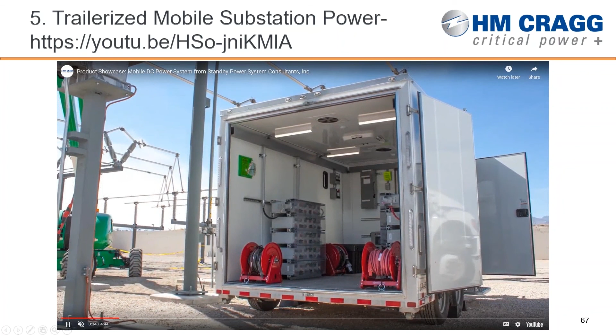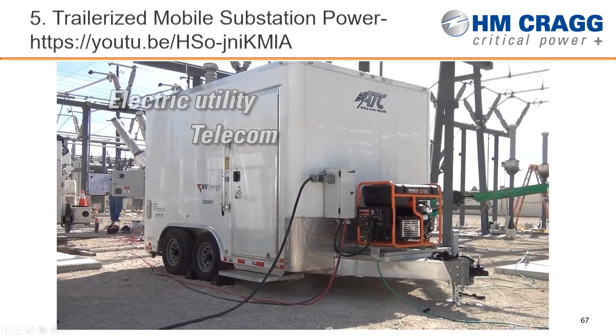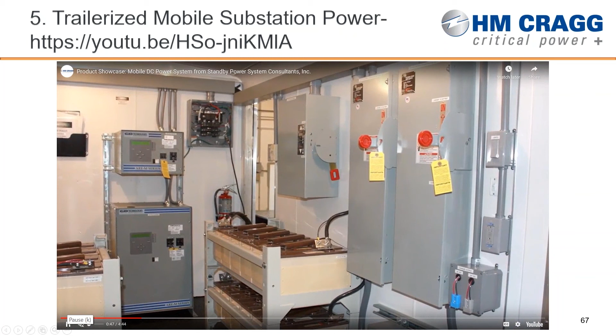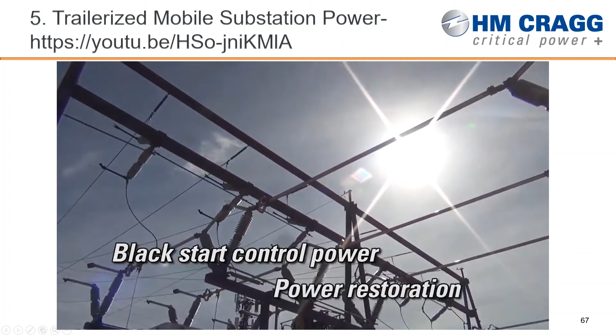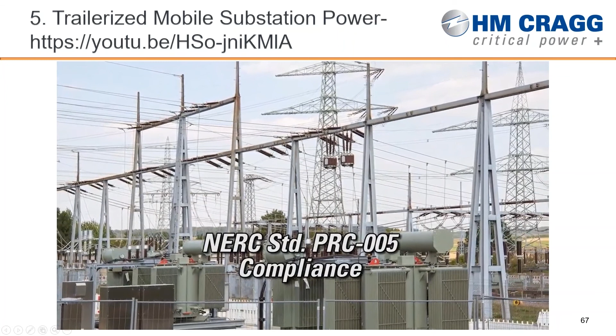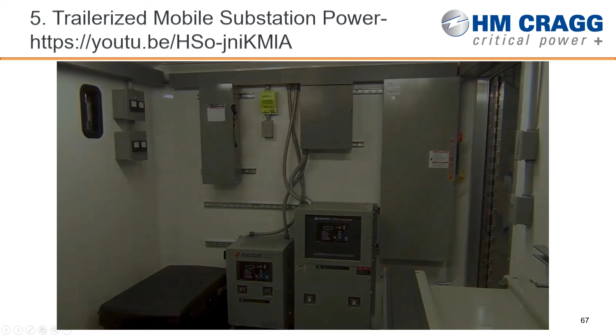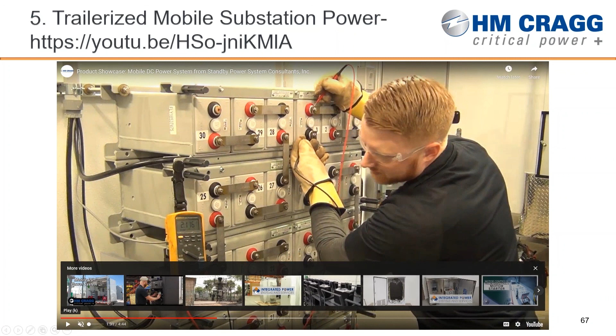The team in Chicago developed this system design based on a heavy-duty trailer system for a dual input AC source with dual voltage output. They have two specific chargers, one at 130 volt DC and one at 48 volt DC, with transfer switches to switch AC sources as well as the DC output. There's a single 130 volt string of front terminal batteries with a split system inside, so selecting 130 volt gives full battery capacity, or you can flip a switch for a 48 volt application. It's a dual input source with shore power available as well as a Generac generator on the front as a standalone source.